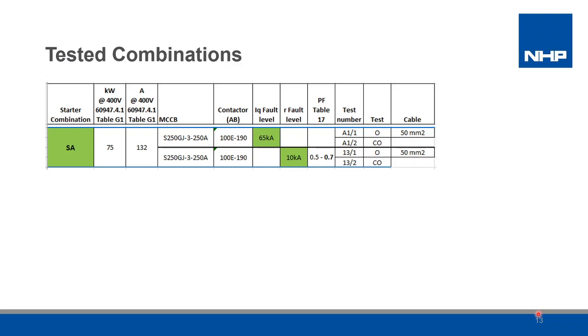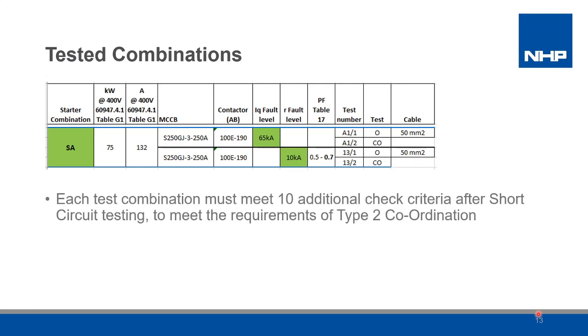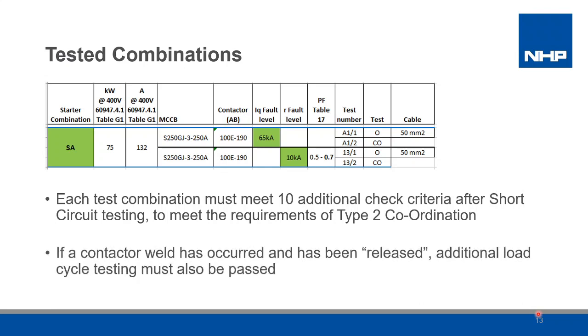For a combination to be verified as Type 2, it has to pass the 4 short circuit tests. Plus, each panel, following the completion of the O and CO sequences, is tested for its electrical properties. This is to ensure there is no damage to the breaker, contactor, housings or terminals, and there's no breakdown of the insulation, phase to phase or phase to earth. As said before, a contactor weld may occur, but to be confirmed as a pass, an additional test of 10 rapid switching on-off cycles at twice the starter rated current has to be completed.